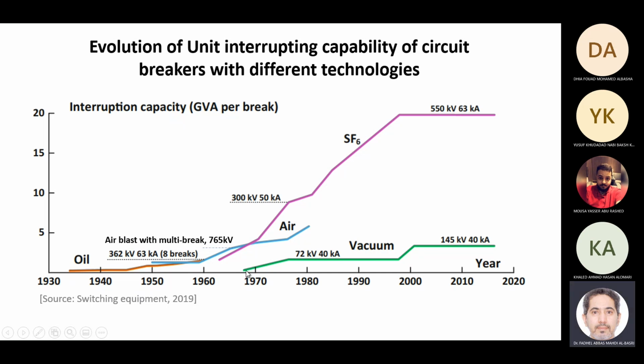In the 1970s, they now have vacuum, which is now commonly used for medium voltage, like up to 145 kV. This is considered a high voltage, but for medium voltage, the majority of breakers are vacuum, and it is still widely used nowadays. I would say 80% of the breakers at the medium voltage levels are vacuum circuit breakers, but they have limited breaking capacities.